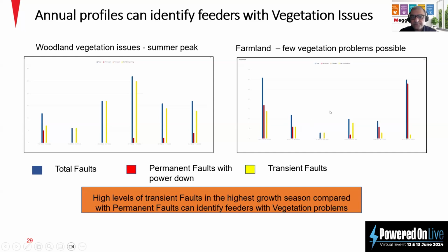While in the farmland, there is no transient fault during the summertime, but in January, February, November, and December, when there is high wind in the area, the permanent fault is growing. That is helping the utilities and managers make decisions.